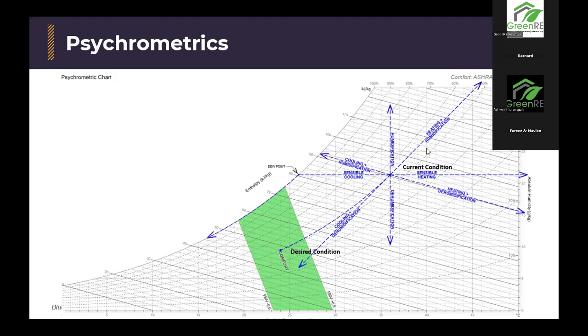This is all the type of cooling and humidification that can happen in a HVAC system. As you can see, the pattern of movement with the mouse, the pattern of movement here, is what is known as cooling and dehumidification. Earlier, remember the SHR, the ratio of coil that is doing sensible cooling and latent cooling. Latent cooling is basically dehumidification. So that is why it is important for you to bring down both, and you get this.